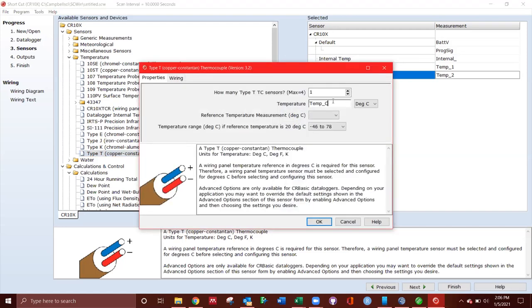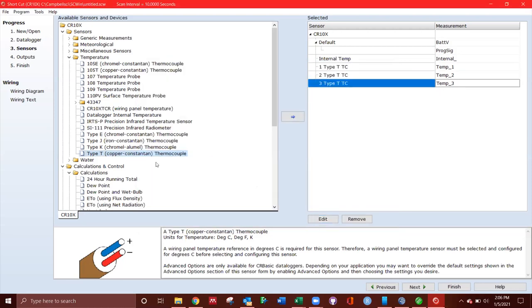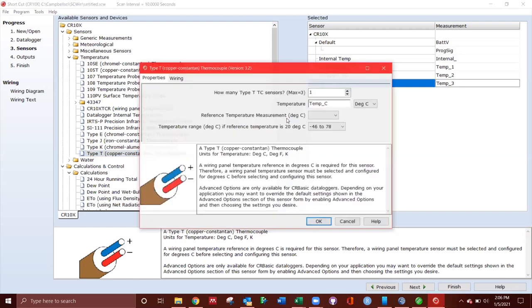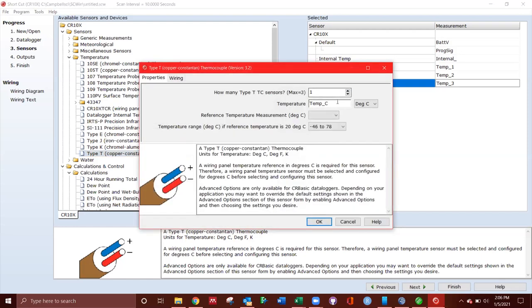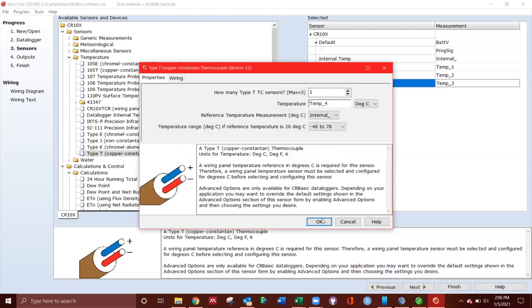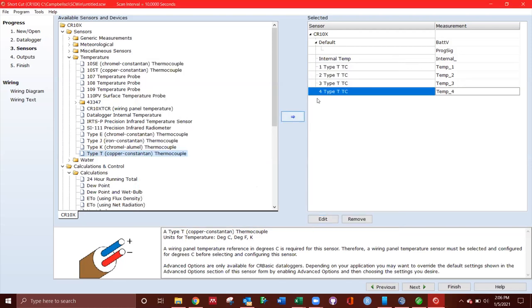Now, when I say reference internal, it does not mean that that is a calibration measurement. When we do actual calibration, putting the thermocouple ends into water along with an additional sensor or a reference thermometer, that is where we generate calibration values. And that's what you go ahead and put back in your program file later on.